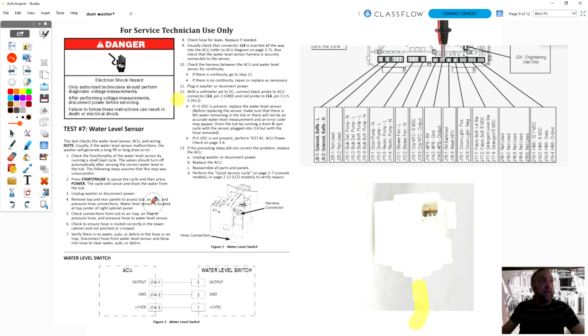So if you had either one of those instances, they want you to check the 5 volts here. Do I need to ohm out my communication wire, the output wire here, J14-1 to pin 3 on the board? Do I need to ohm that out? Probably not, because if there was a connection problem between the top wire here, we'd get an error. The board would shut down. Because if it cannot communicate to that water level sensor, it doesn't mean the sensor is good, but if it can't communicate to it, it'll shut down. If you disconnect that plug and try to run the machine, it won't work. It's going to tell you, I can't see the water level switch as a safety device.